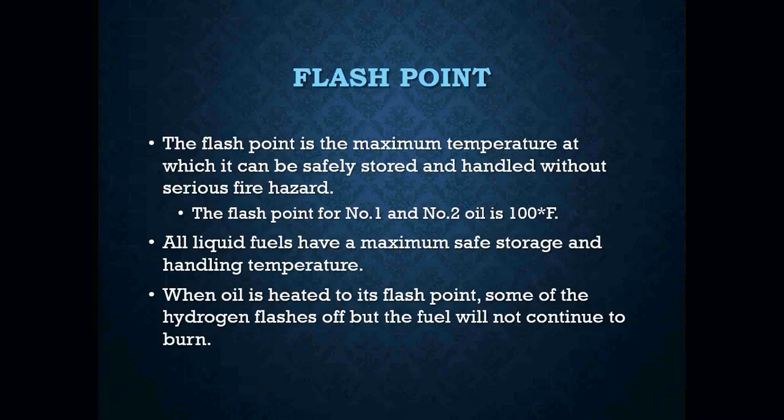That's the magic number. Flash point is the maximum temperature at which it can be easily stored and handled without serious fire hazard. So the flash point for number 1 and number 2 heating oil is 100 degrees. Now again, all oils, all liquid fuels are going to have a maximum safe storage and handling temperature. So when oil is heated to its flash point, what's going to happen is that some of that hydrogen is going to flash off. But the fuel will not really continue to burn. It's going to flash off and then it's kind of going to die out.